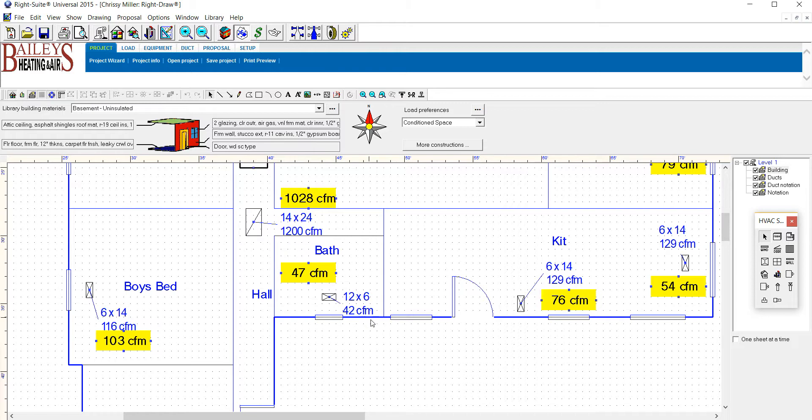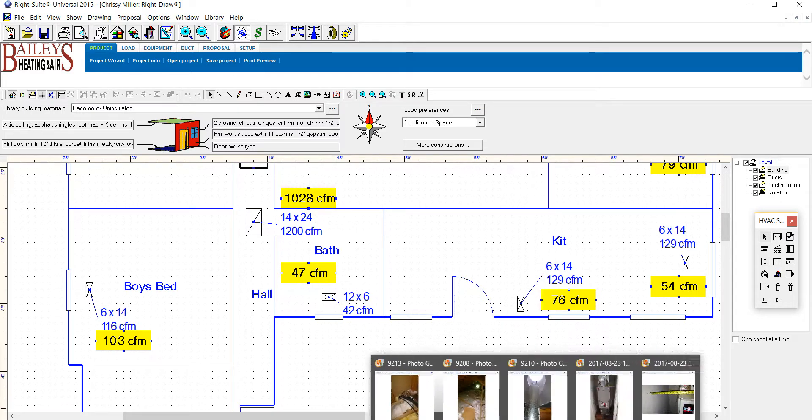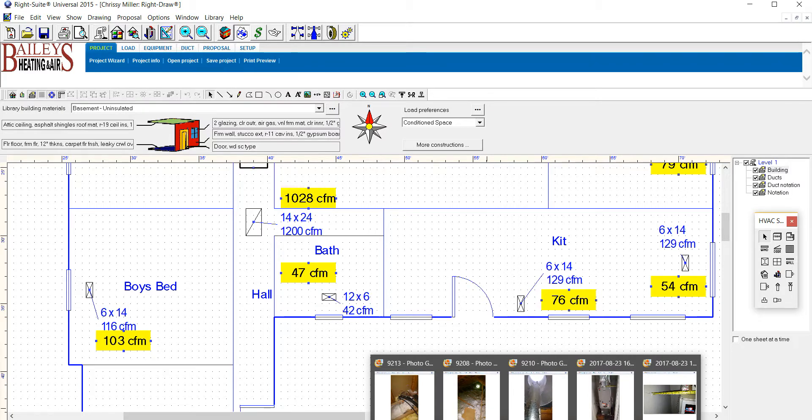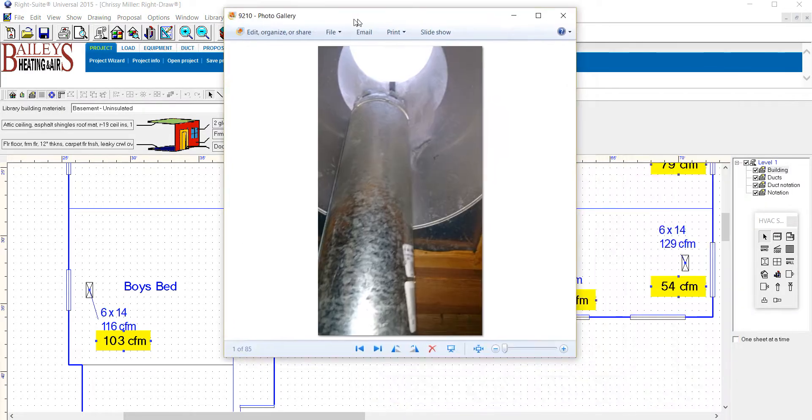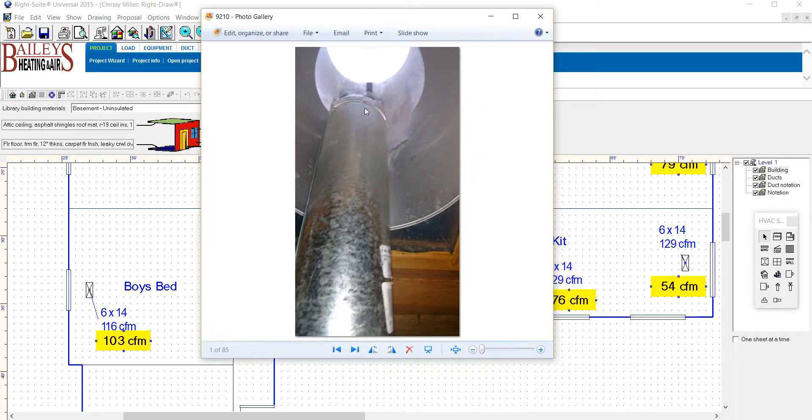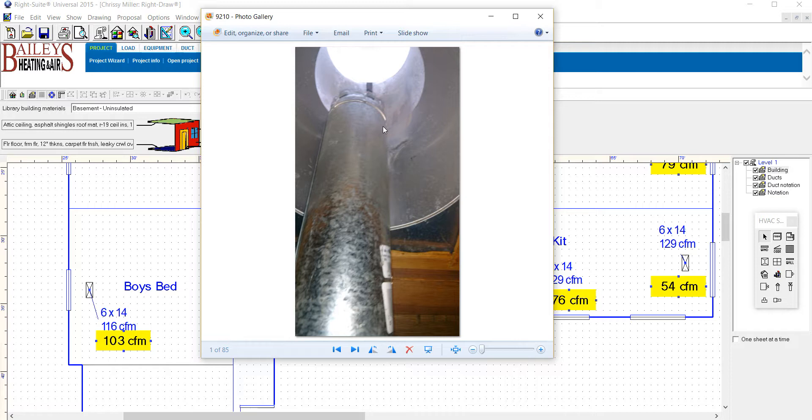One other thing too, there was a huge hazard and this is your flue in your attic. It is not going all the way through the roof. Do not run your heater till this is fixed. I gave you a price to take care of this part and I'm amazed that the house inspector did not catch this. This needs to go all the way up to the roof, otherwise it'll spill gases into the attic. That's why this is discolored right here. That could be deadly. It could potentially kill somebody if it's making any carbon monoxide. So this is something for sure that should be taken care of.